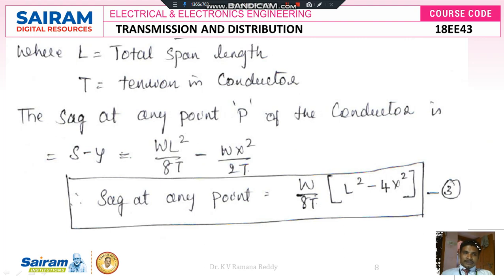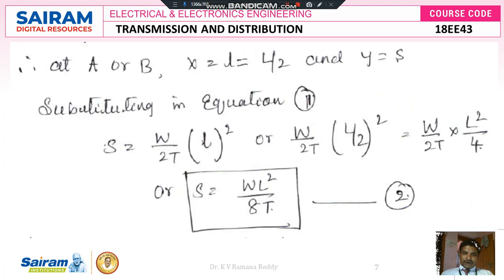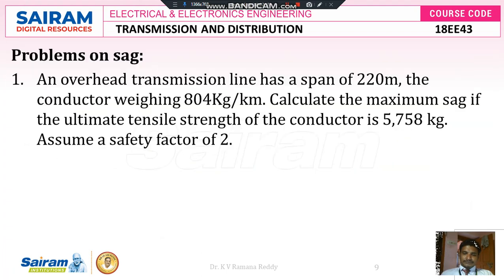Multiplying through gives the maximum sag formula: S = wL²/8T, where capital L is the total span length and capital T is the total tension of the conductor. The sag at any point P is S − y = wL²/8T − wx²/2T = (w/8T)(L² − 4x²). The maximum sag formula is S = wL²/8T.